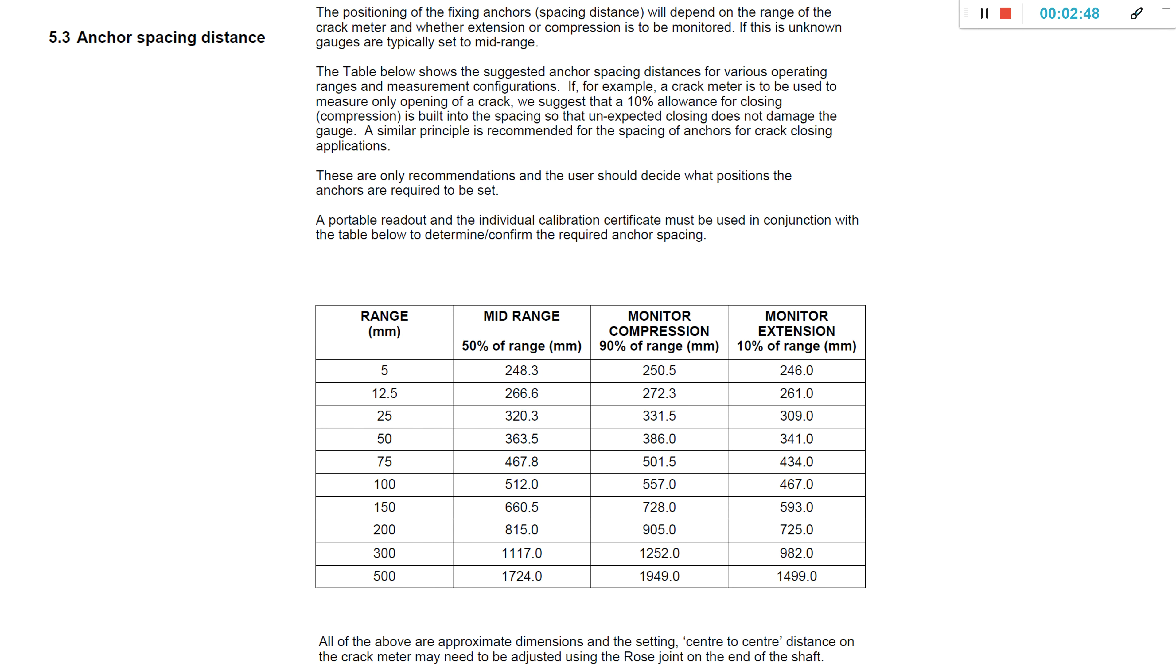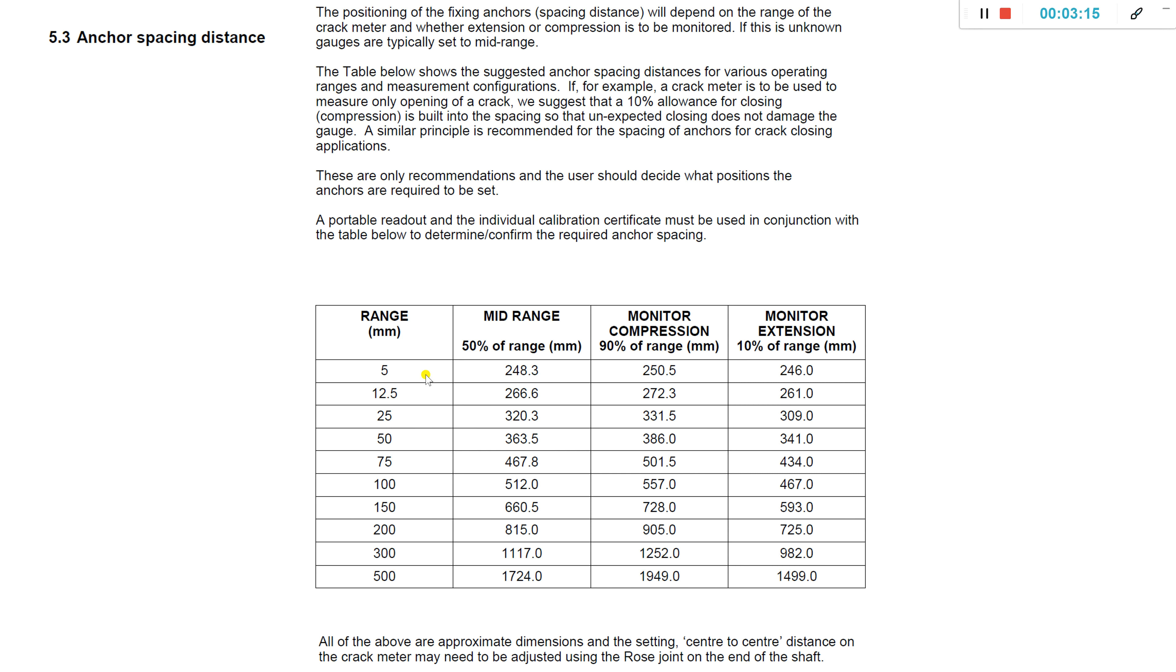You can obtain the manual from Geosense for how to install a vibrating wire crack meter. In terms of understanding the key aspects, this page shows you the range. Column A, you have different range versions from five millimeter down to half a meter. If expecting expansion or contraction, column B is the length in millimeters to set such that you're at the midpoint.